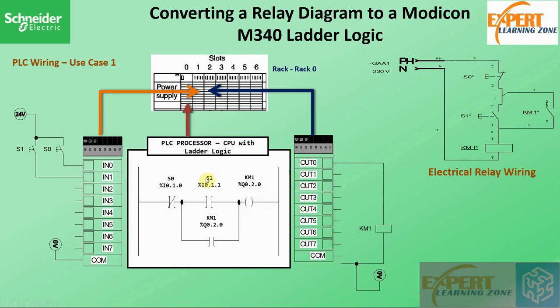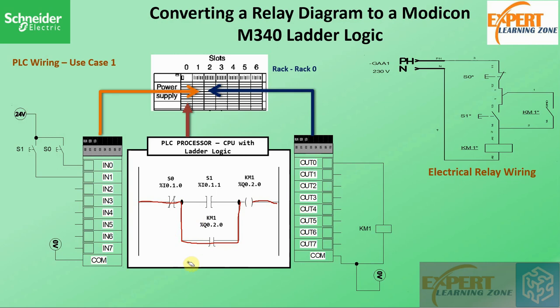At that instant, if I release my hand from S1, this path becomes true. The S0 contact is normally closed, so current is already present there. When I press S1, that contact closes and current flows to the output — the coil is now latched. The contact of that coil is energized and this parallel path now becomes true, acting as a hold-on path. When I release S1, it goes back false, but the hold-on path keeps the system constantly on.